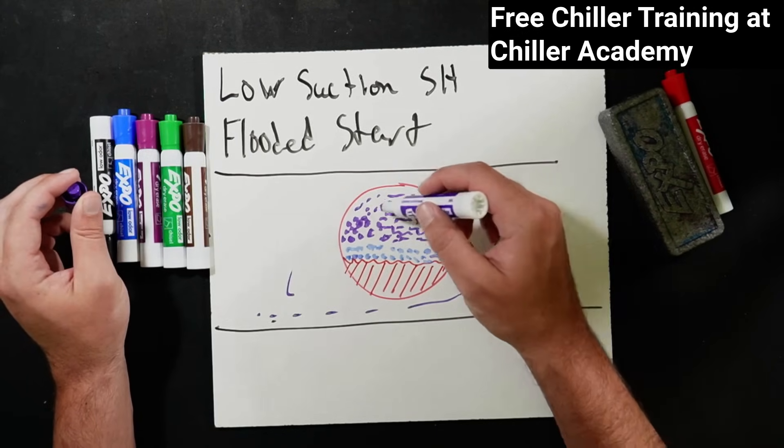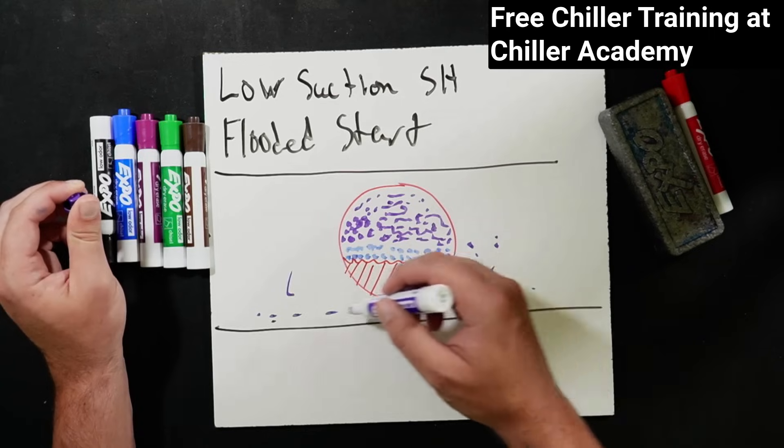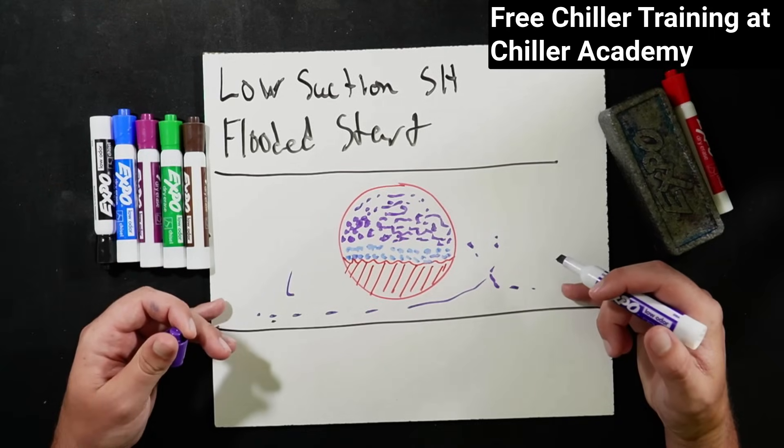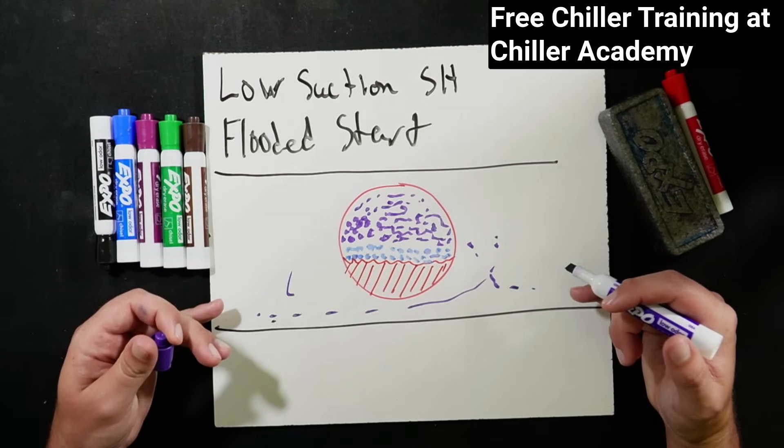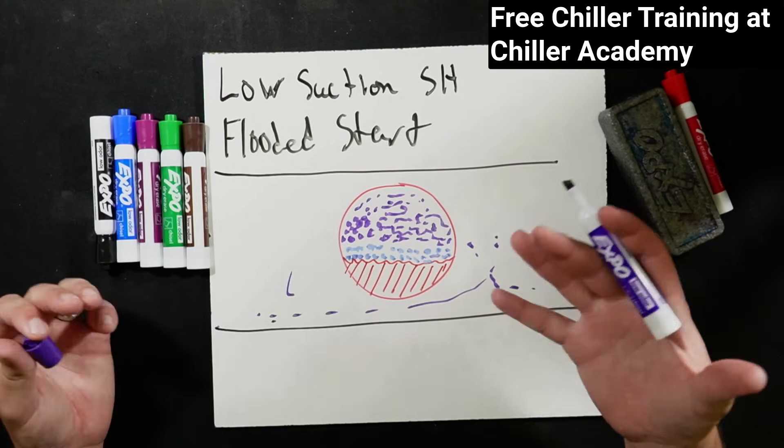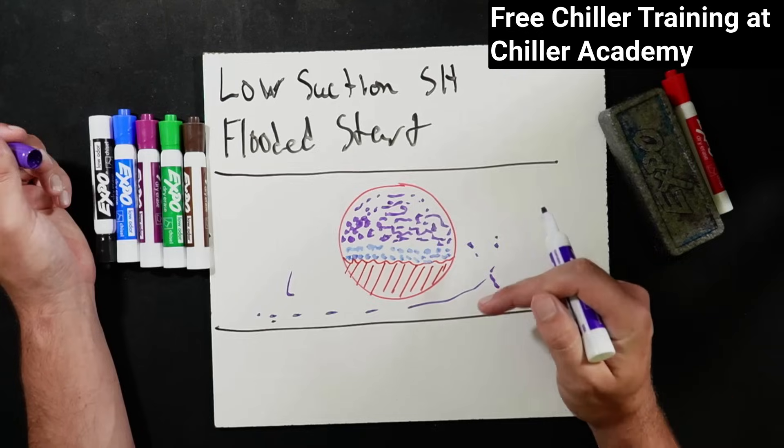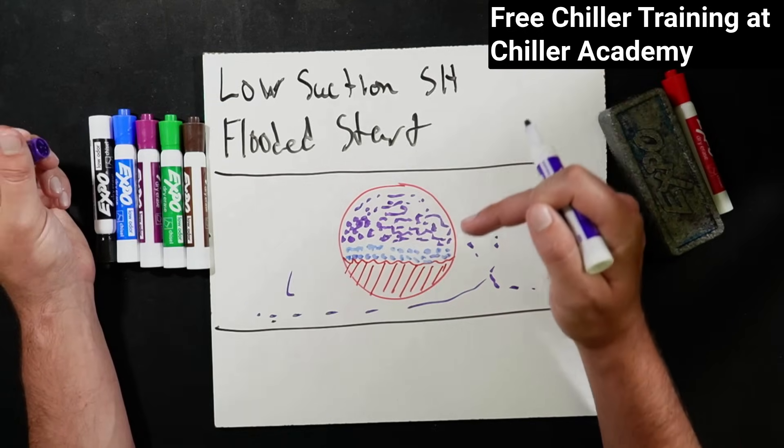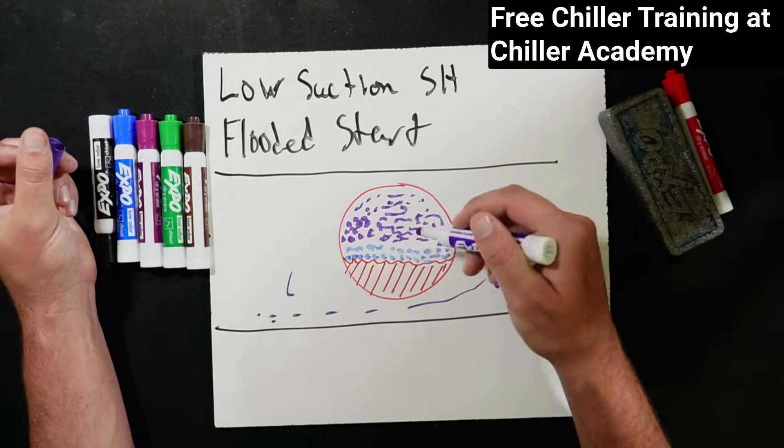And in that situation, it comes back to the liquid refrigerant stacking in the bottom of the sump or the oil reservoir, which is built into the compressor and that getting stirred up is flashing that off, creating the foaming action.